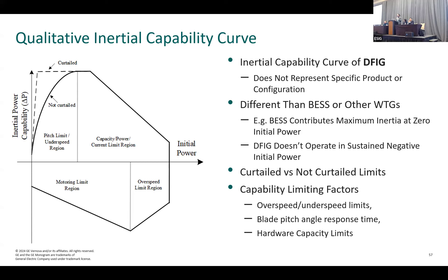This is quite useful and important, though many people dislike hearing that inertia contribution depends on time of day, operating conditions, and controls — people want a single number like 5, 3, or 4. Unfortunately, it's not that simple. Regardless of where you draw the line, you will either underestimate or overestimate the inertia for a given operating condition.